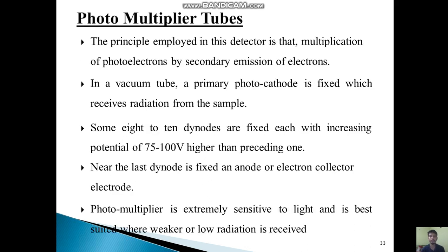The last one is the photo multiplier tube. The principle employed in this detector is the multiplication of photoelectrons by secondary emission of electrons. In a vacuum tube, a primary photocathode is fixed which receives radiation from the sample. Some 8 to 10 dynodes are fixed, each with an increasing potential of 75 to 100 volts higher than the preceding one.